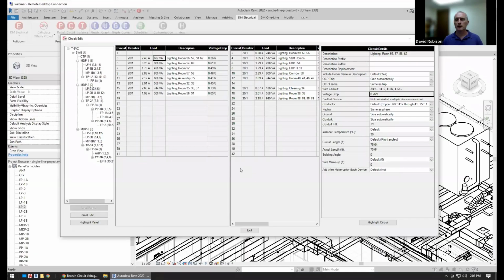There's a question: what's the reasoning for our default of EMT less than 2 inches and PVC for 2.5 or greater? The reasoning is just that that's what the engineers we work with have said they generally like to specify. They prefer EMT for the smaller circuits. When they get bigger, they switch over to using PVC conduit. So by default, that's how it's set up. Usually that's how it should be in the specification, so we just call it out that way. But we do try to make it clear in our wiring ampacity that that's why it is.